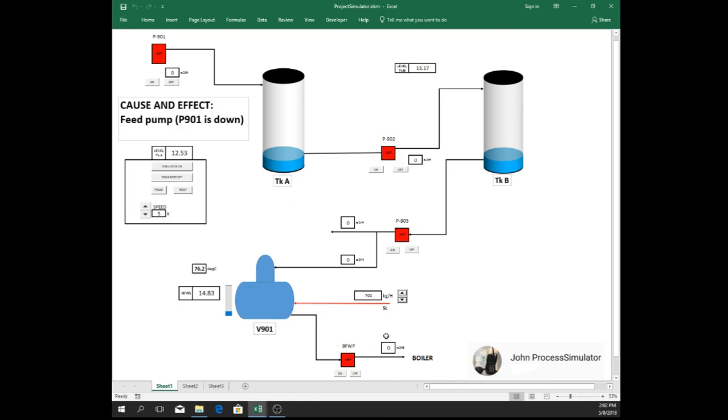And now our boiler feed water pump is tripped as well because it reached below 15%. So as you can see, our plant is now tripped.